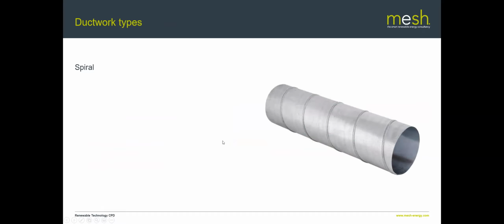So what are the actual ductwork types? Well, probably the one that's cheapest and people may be more familiar with from commercial applications is a spiral wound galvanized steel ductwork like this. It's cheap as chips. It's brilliant in commercial applications. It's very suitable for a lot of domestic applications as well, especially where you've got a reasonable ceiling void.